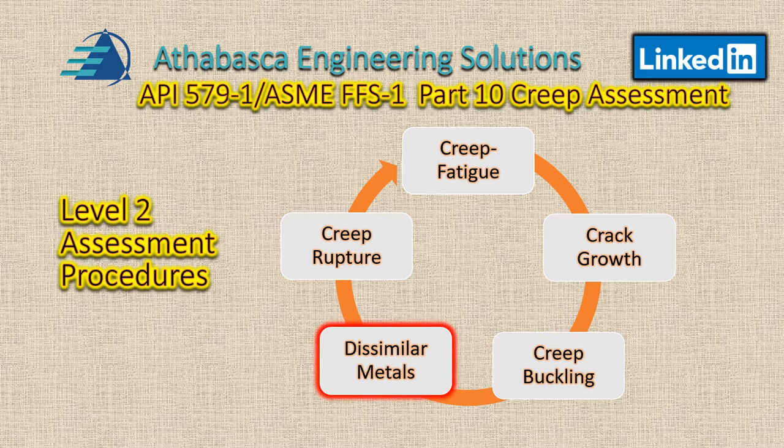CREEP fatigue assessment of dissimilar metals is referred to in section 10.5.6, and it is applicable to 2¼Cr-1Mo materials, 2¼Cr-1Mo vanadium, austenitic stainless steels, and other dissimilar weld metal joints made of stainless steel or nickel-based filler metals. This is for very high temperature, heat-resistant materials.